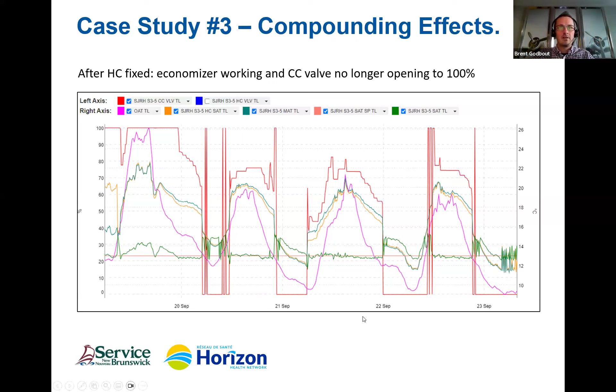So this is overnight, this is our cooling energy overnight. You can see it's about the same as during the day on this air handling unit, and this was while that heating coil valve was passing. Then once we fixed it overnight, now we're not using any cooling, unloading our chillers. Then when the temperature goes up during the day, we're using a lot of cooling energy, as expected. It's warmer during the day.